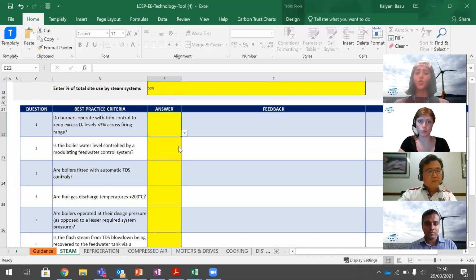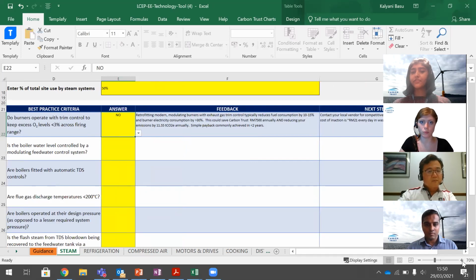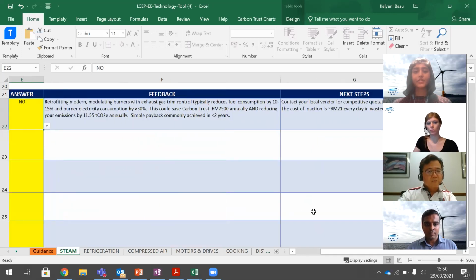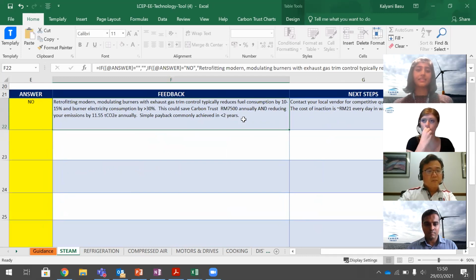So in this case, I will say no. And then you get some immediate feedback. So in this case, you can see that it's telling us that because we're not aligned, we should consider applying this best practice, because retrofitting modern modulating burners with exhaust gas trim control typically reduces fuel consumption by 10 to 15% and burner electricity consumption by more than 30%. So in this case, it could save our company about 7,500 ringgit annually, reduce our emissions by 11 tons annually, and you have the simple payback calculated as less than 2 years.